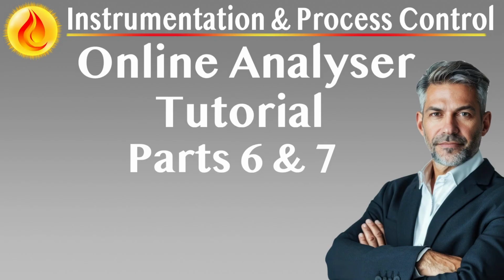Instrument air supply. A clean, dry, and reliable instrument air supply is essential for the operation of pneumatic actuators, sample conditioning components, and purging of certain analyzer systems. Instrument air should conform to the requirements of ISO 8573-1, typically class 2.2.2 or better, meaning a dew point below -40 degrees Celsius, oil content less than 0.1 milligrams per cubic meter, and particle size under 1 micrometer.